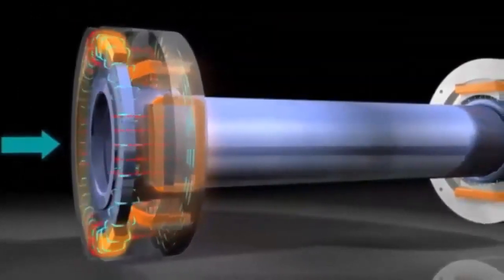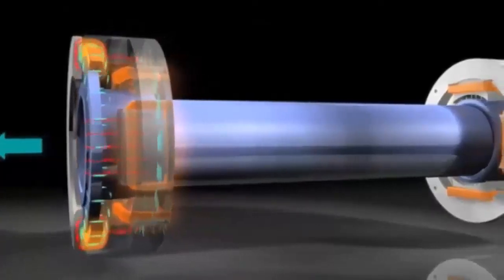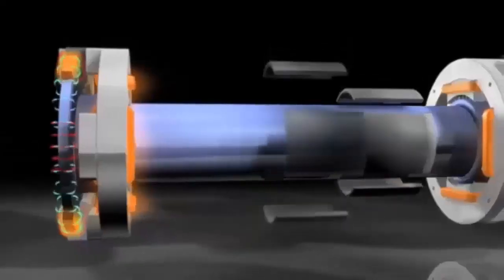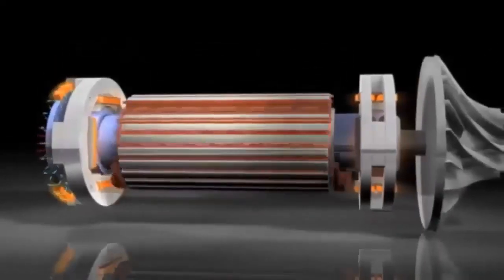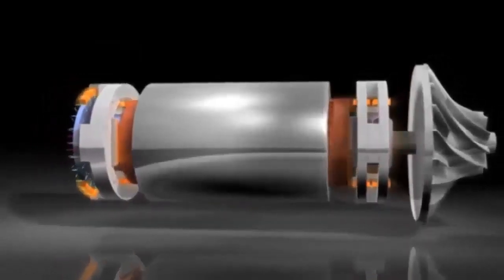These chiller equipment can also further increase the efficiency when they use economizer containers with economizer to then be able to take advantage of the flash gas that is produced in the expansion. We can also see that these compressors use a synchronous type motor. This will also help to further increase the performance of this type of machine.